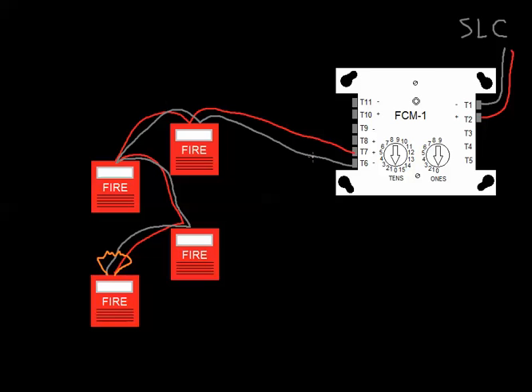But when these devices have to come on, they're triggered through programming. So something in the programming, just like with all the other modules, I would set an address on this module. I would tell it this is address 8 maybe, so I'd leave 10s at 0 and I'd move the 1s to point at 8.